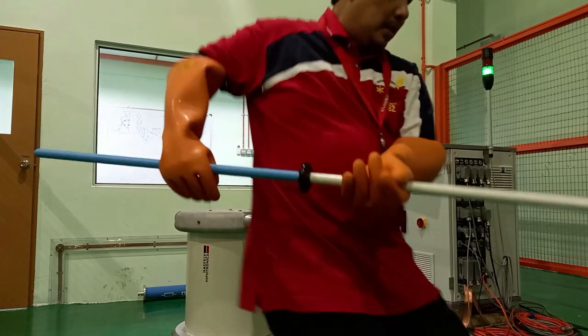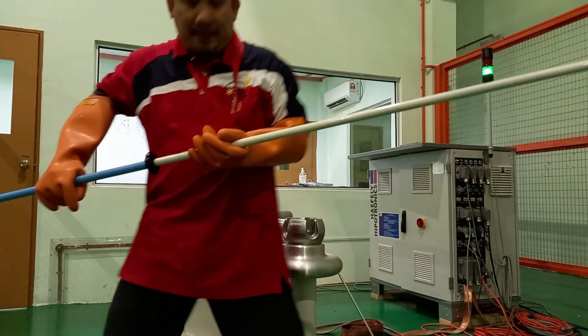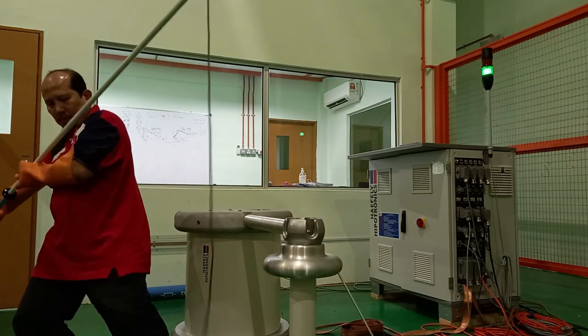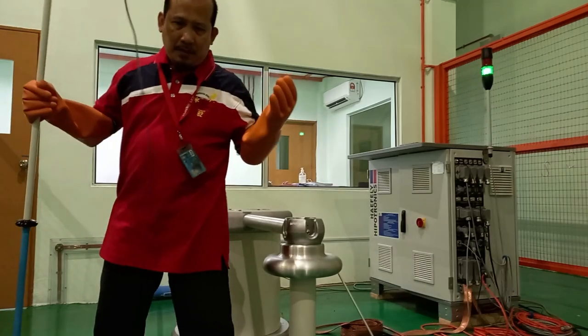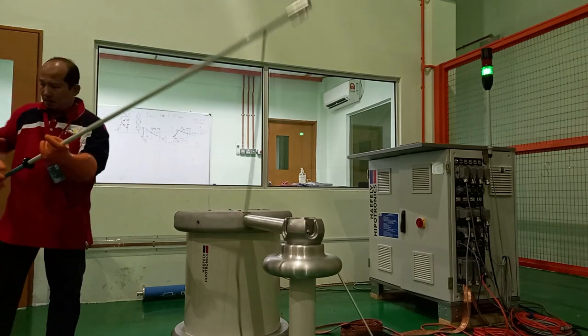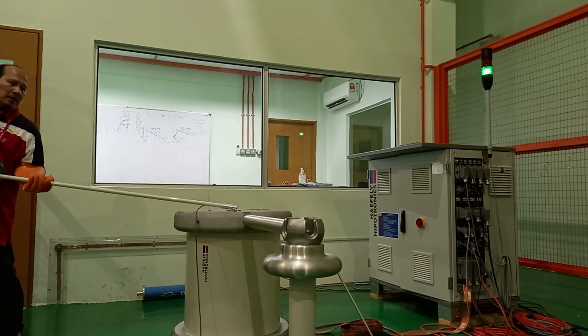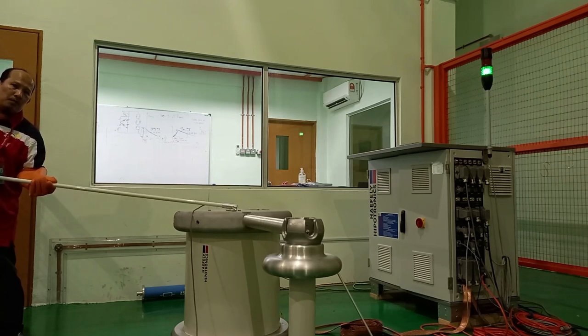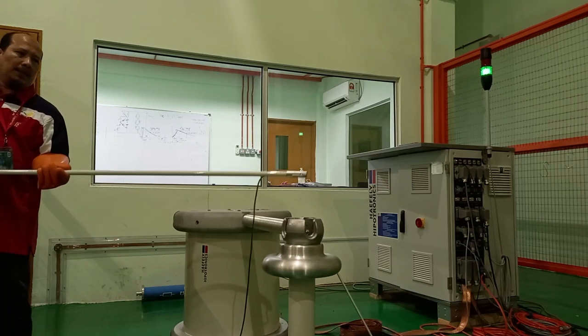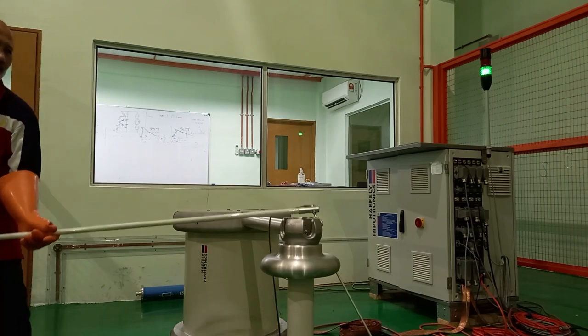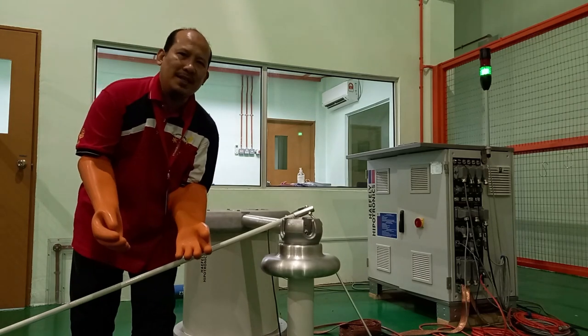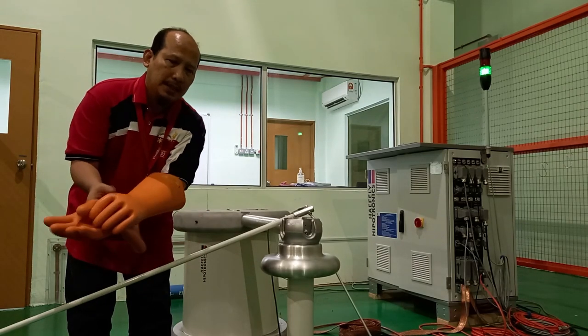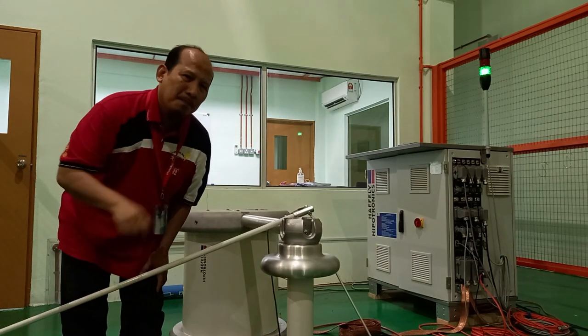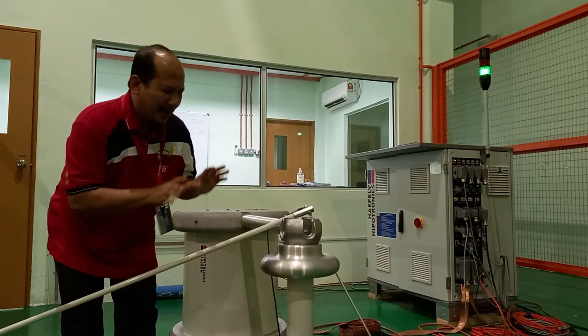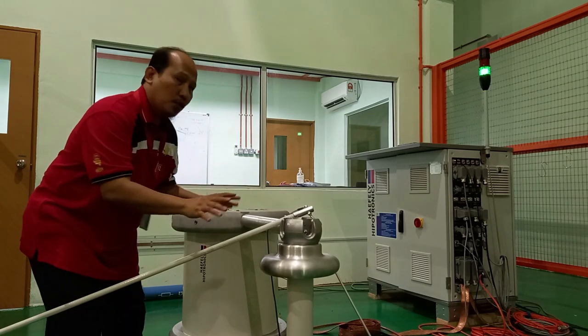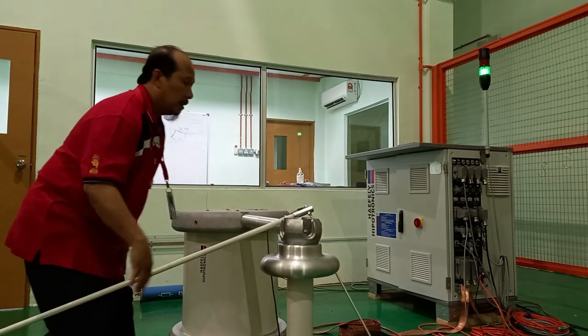Also, you should not cross. Here we have a cable, right? You should not cross like that. Please ensure to discharge. You have to begin from this section, the transformer, then move to the conductor and then go to the capacitor. Then you should be safe. Of course it is not very convenient, right? So then use another glove. There is also a very small amount of charge, but by right, all the charge from this side should already be removed nicely. Just a moment.